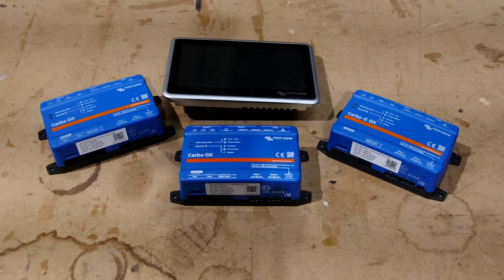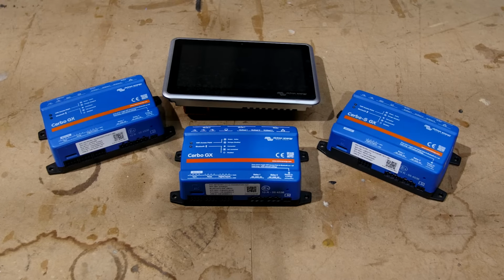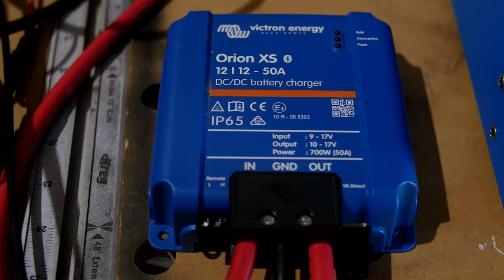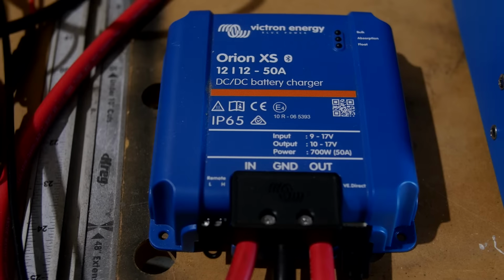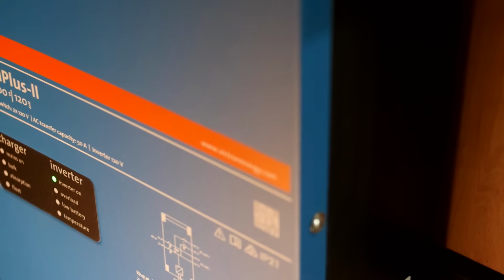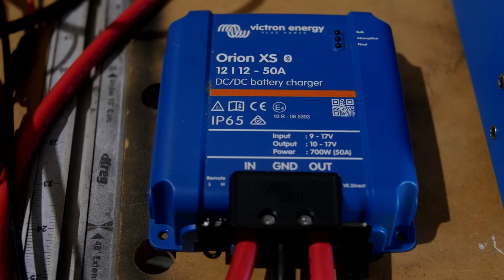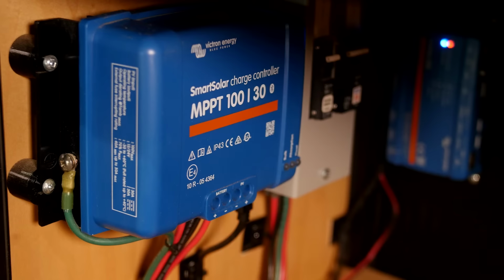DVCC is unlocked by having a GX device in your system, such as one of the many Cerbo devices or an Ekrano, which serves as the computer or the brains of the operation. Once you have the GX device, pretty much any Victron charger with a data connection can work with DVCC. That's anything with a VE Direct, VE Bus, or VE CAN port, including products like the newer Orion XS 50 amp DC to DC charger, solar charge controllers, inverter chargers, and so on.